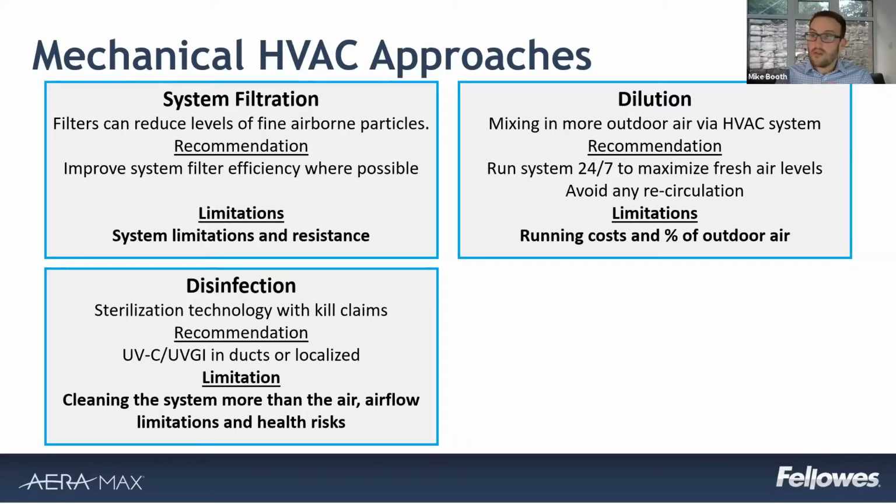You need the right amount of energy or power. It needs the right contact or dwell time with whatever it is that it's trying to clean. And it needs that right level of exposure and an overall balance of all those factors in order to be as effective as possible. Just simply introducing a UV light into an existing airflow system is not the right solution. And we see that both with air purification units, but also with in-system approaches as well. And there are also some health risks. You don't want to be exposed to this type of light, to the eyes, to the skin, and that's something to be cautious of as well.